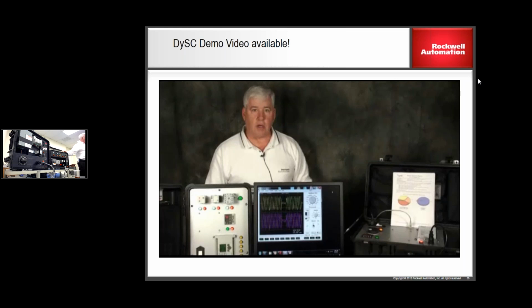And we see the same fault. Even though this thing is down to barely a cycle in duration, and it's a very mild sag, this relay dropped offline. Now the PLC is running, so in your manufacturing environment, what would happen? Imagine this was your controls and your compressor. The controls are going to shut the compressor down because this wasn't supposed to happen.